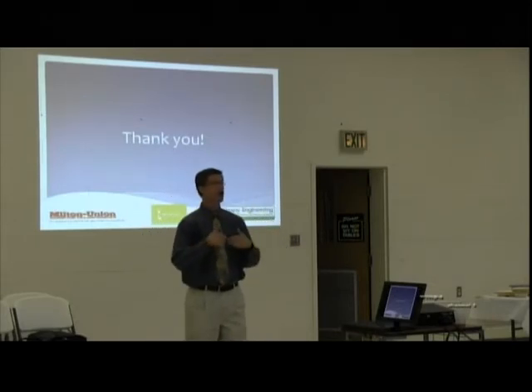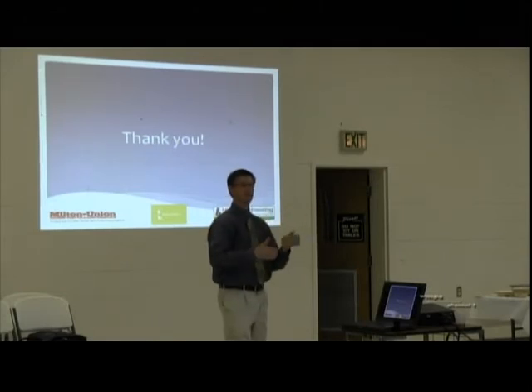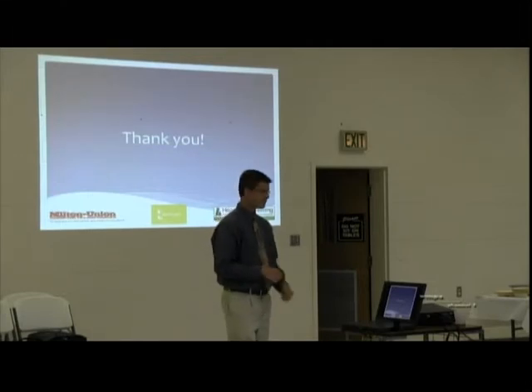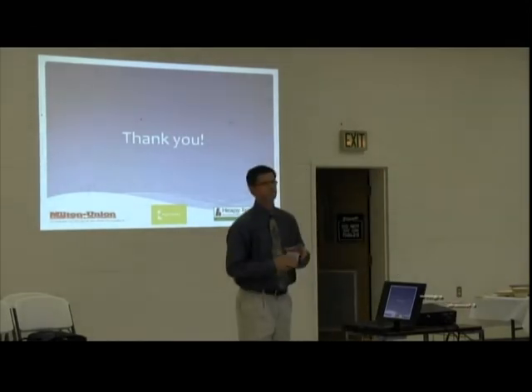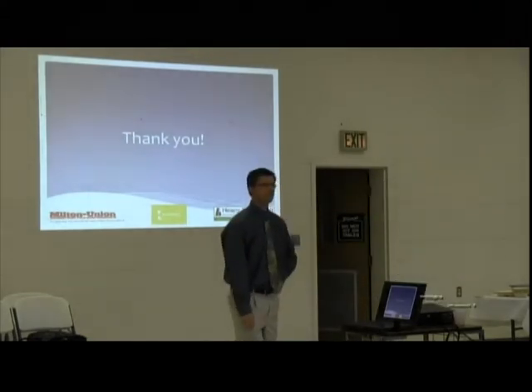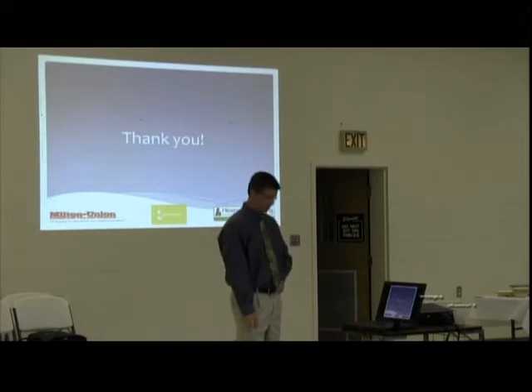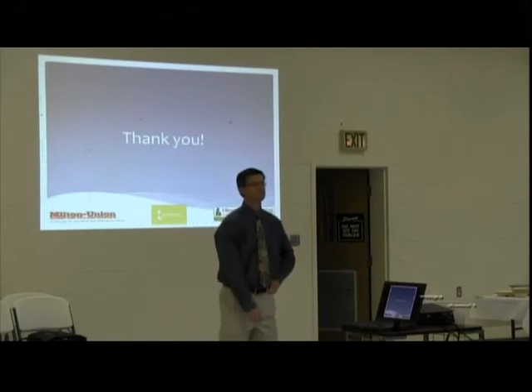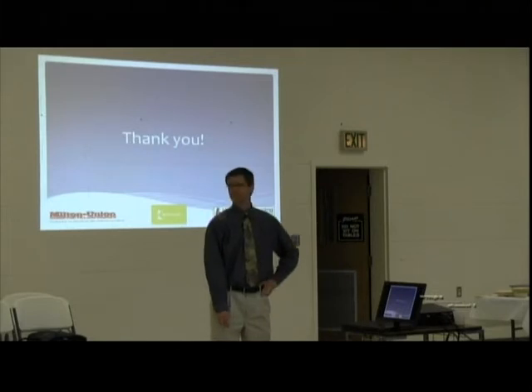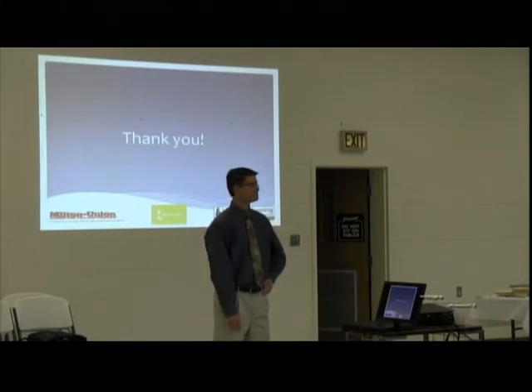Because now we have to have like 100% outside air to exchange, and I can't remember exactly what the rate is. There's significant outside air brought in through the air handling units. But part of the energy saving piece that Mike's talking about is that rather than air leaking in where you don't want it, which can cause cold drafts, you focus all of that outside air in the air handlers. The majority of the air handlers, if not all, have what are called energy recovery wheels, where the outside air is preconditioned by exhaust air, and you recover some of that energy from the heat exchanger. That saves energy rather than just having to heat your pool from 0 to 70.